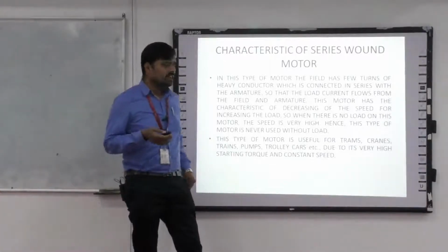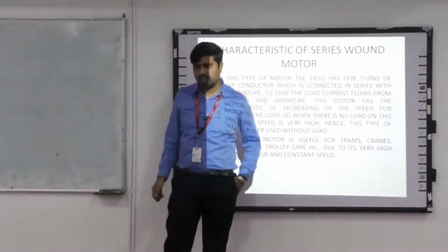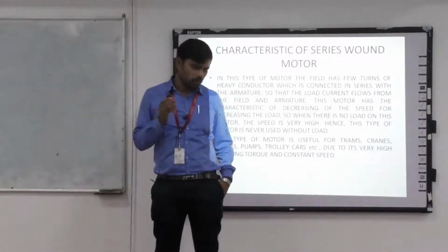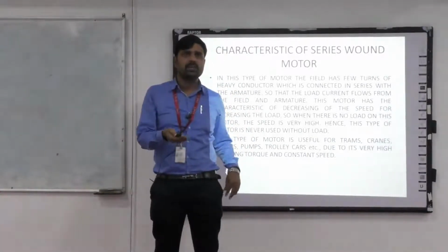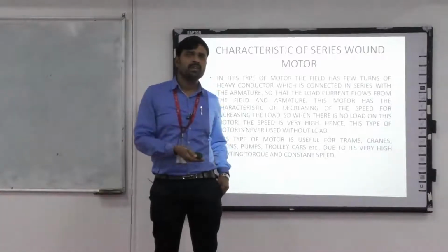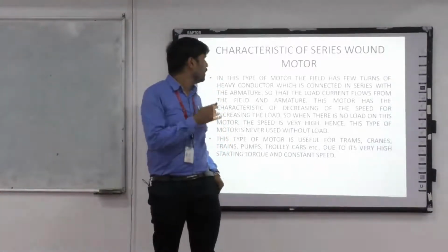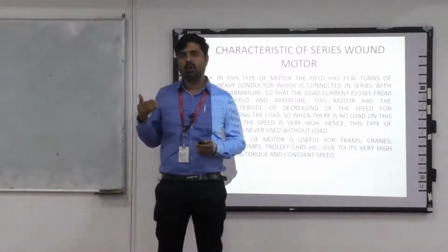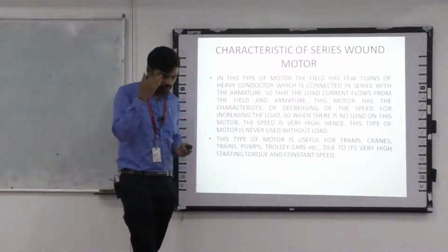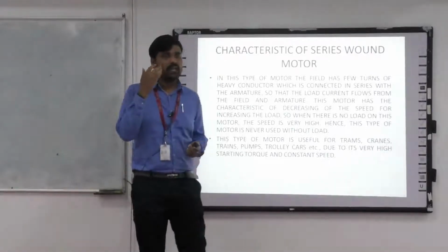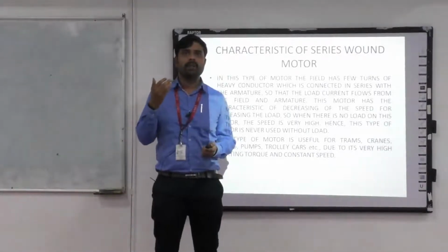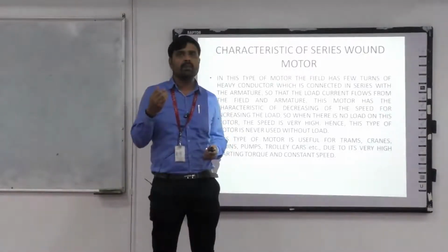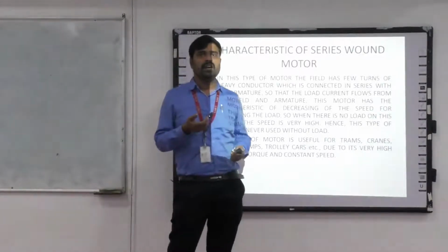Next one is the series wound motor. If we see a shunt motor, the shunt motor can be operated without load, because we are maintaining a constant speed and starting it gradually by means of a 3-point starter. But a series motor should be operated with load only. Why should we start with load? Because N is proportional to Eb by φ, right? At the time of starting, when the flux is very minimum, the speed will be very high.